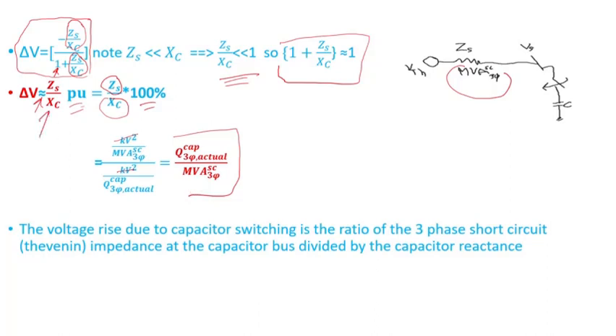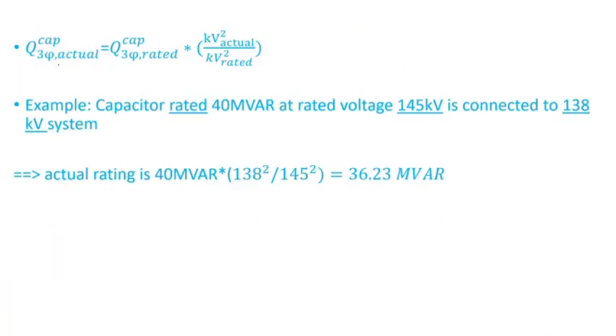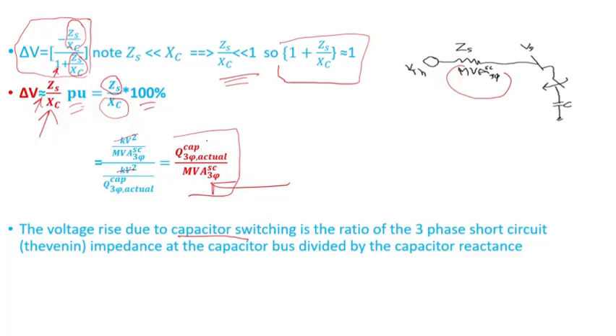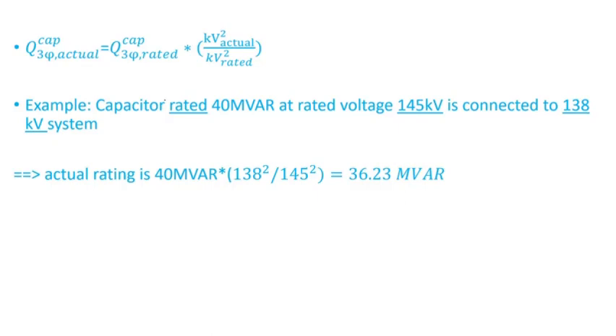So this formulation applies whether you want it in impedance form or in MVA, MegaVar, KVar, or KVA. The voltage rise due to capacitor bank switching is the ratio of the three-phase short circuit Thevenin impedance at the capacitor bus divided by the capacitor reactance, or equivalently the actual three-phase rating of the capacitor bank divided by the three-phase short circuit MVA. The actual rating of the capacitor bank equals the rated value from the manufacturer times the actual system voltage divided by the rated voltage of the capacitor bank — all squared.